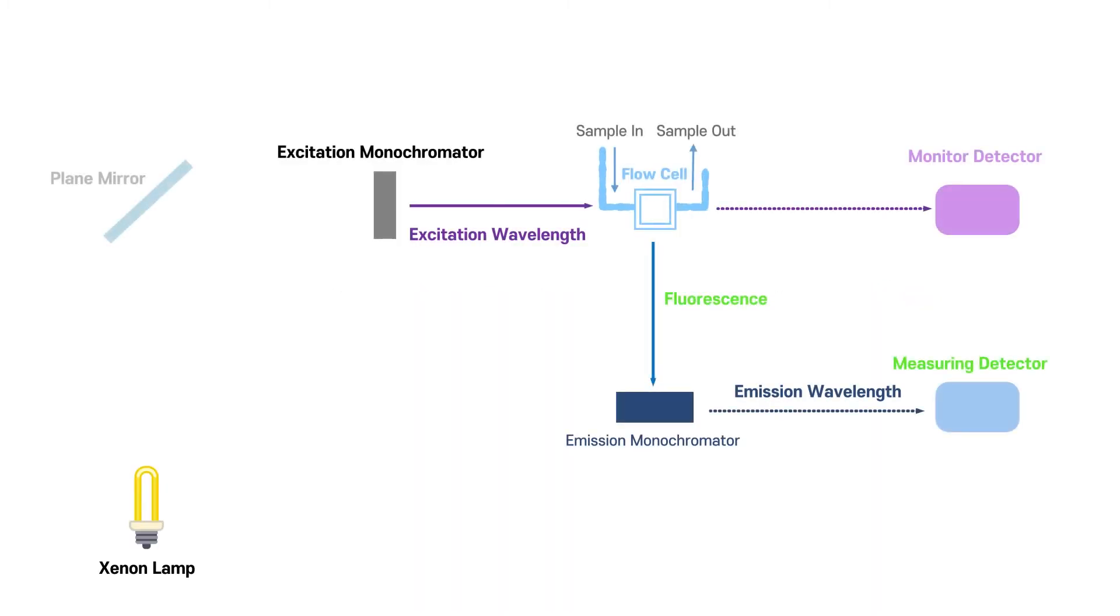The xenon lamp is typically used as a light source to provide light at wavelengths ranging from 200 nanometers up to 700 to 900 nanometers. When it irradiates the light, there can be a plane mirror to change the direction, and the excitation monochromator selects the desired excitation wavelength for the compound.